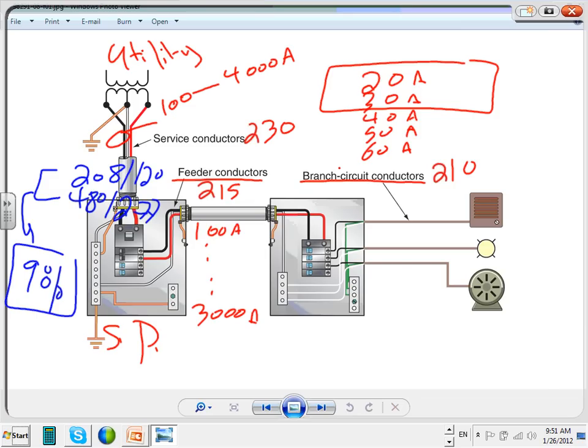I want to bring to your attention, guys, when you are at the service panel, remember what we did here? Right at the service, we have something called the grounding electrode conductor. We size it. We have something called the main bonding jumper, and we size this. Can you see how we bond at the service? We don't bond here. Can you see the neutral and the ground are not bonded, only bonded at the service? And you also have this called the service disconnect means.